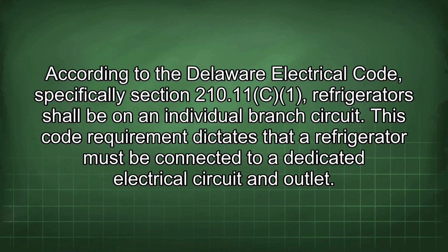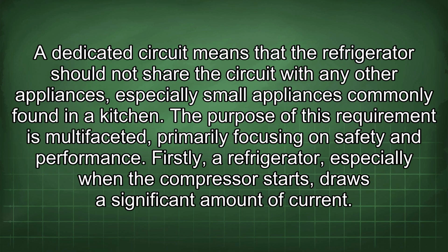According to the Delaware Electrical Code, specifically Section 210.11(C)(1), refrigerators shall be on an individual branch circuit. This code requirement dictates that a refrigerator must be connected to a dedicated electrical circuit and outlet. A dedicated circuit means that the refrigerator should not share the circuit with any other appliances, especially small appliances commonly found in a kitchen. The purpose of this requirement is multifaceted, primarily focusing on safety and performance.